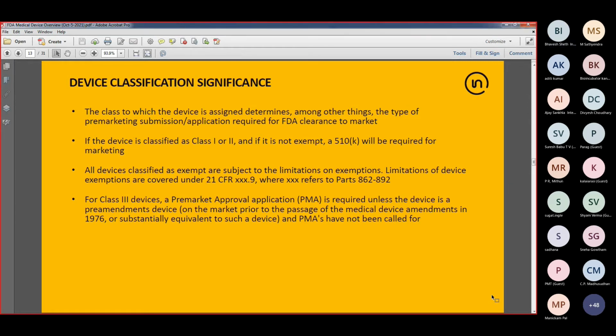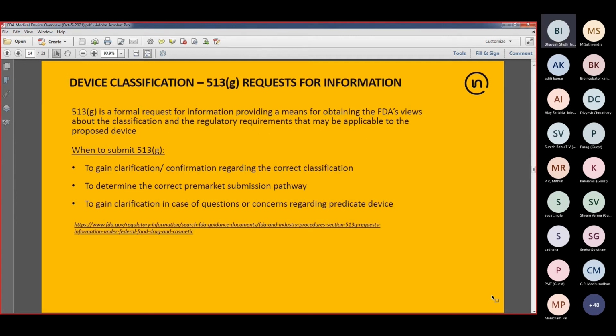What if you have a product for which you can't find the device classification, or for which FDA hasn't established a category at all? For that kind of situation, you have an option to reach out to FDA by submitting a formal inquiry, which is also referred to as 513G, where you are requesting information from FDA. So it's a formal request where you provide FDA details about your device and get FDA's written feedback about the classification and what kind of regulatory submission requirements will be applicable.